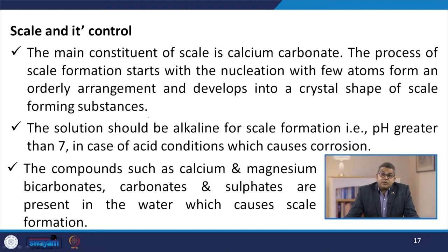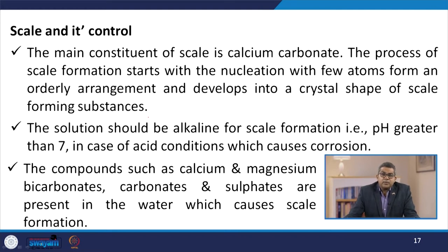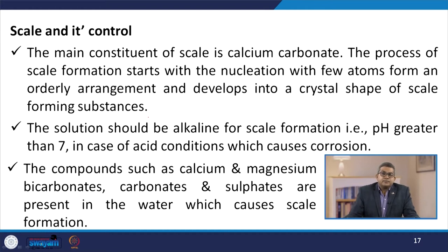Scale is a very crucial aspect in cooling tower operation. The main constituent of scale is calcium carbonate. The process of scale formation starts with nucleation — a few atoms form an orderly arrangement and develop into a crystal shape of scale-forming substances. The solution should be alkaline for scale formation, that is pH greater than 7; acid conditions cause corrosion. Compounds such as calcium and magnesium bicarbonates, carbonates, and sulphates present in water cause scale formation.